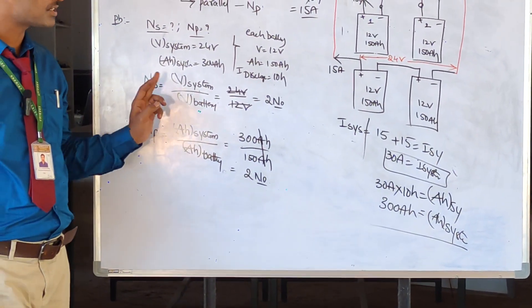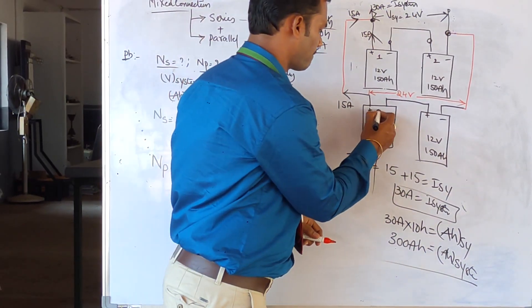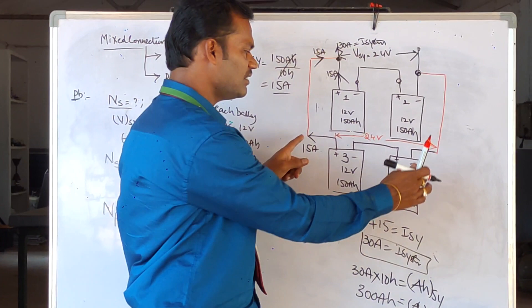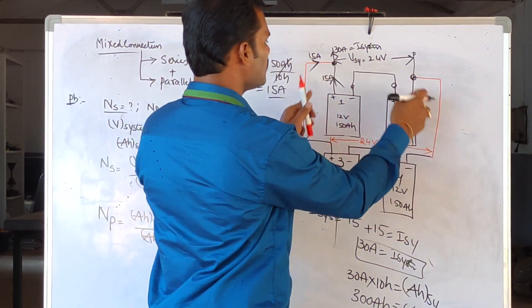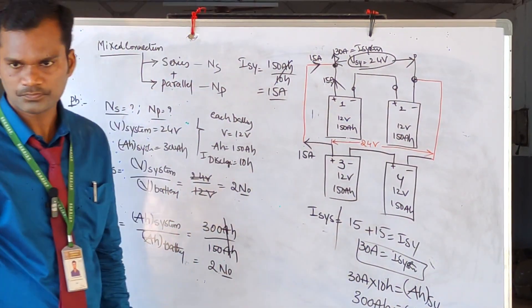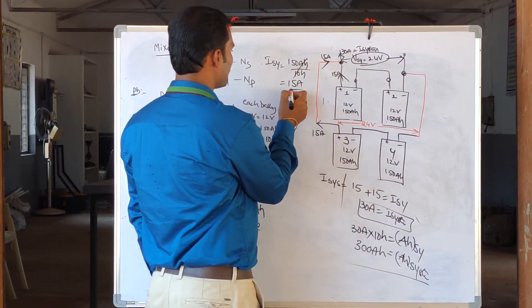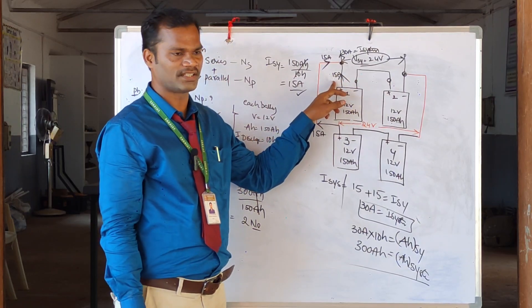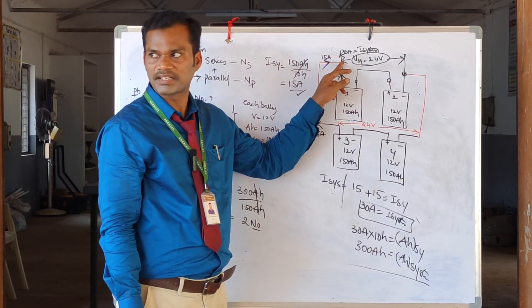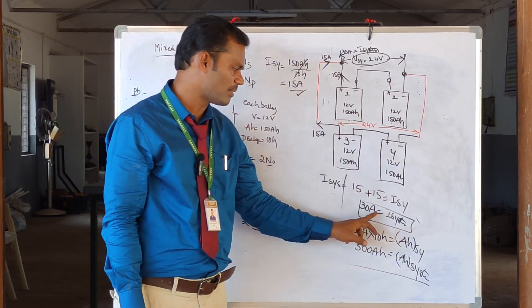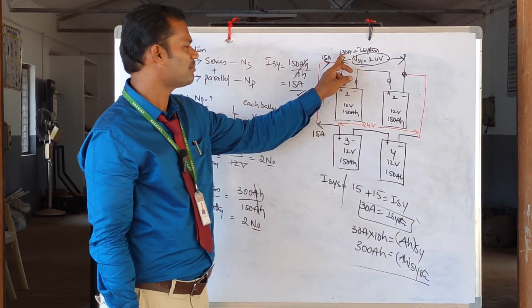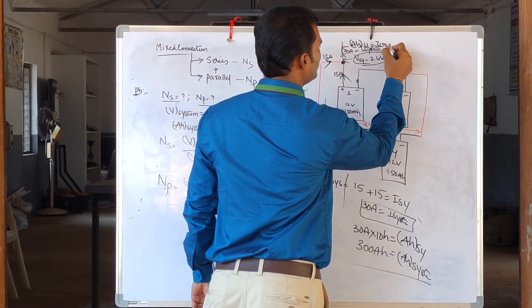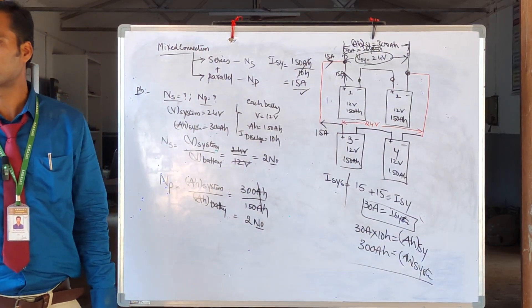To summarize: the first and second batteries are connected in series to generate 24 volts. The third and fourth batteries are also connected in series generating 24 volts. Both series sets are then connected in parallel. Each set supplies 15 Amperes, so applying KCL, 15 + 15 = 30 Amperes is the system current. The total AH capacity is 30 Amperes × 10 hours = 300 AH, which is the required system capacity.